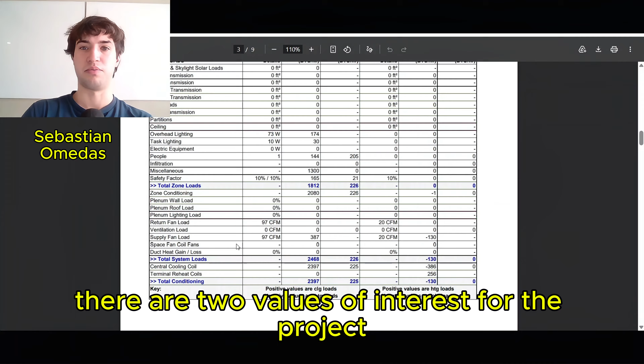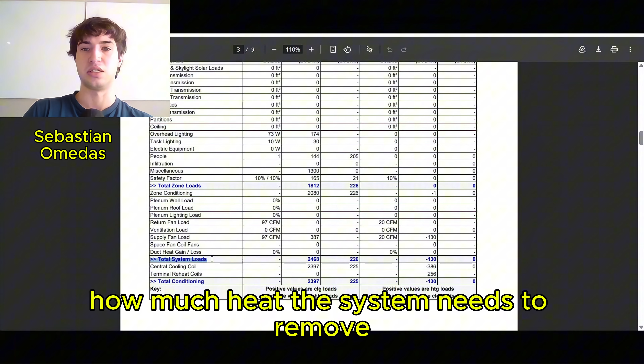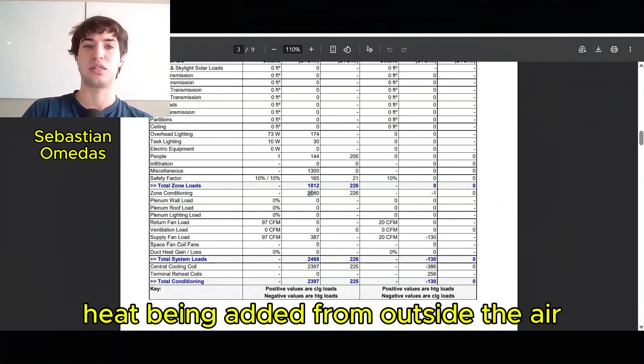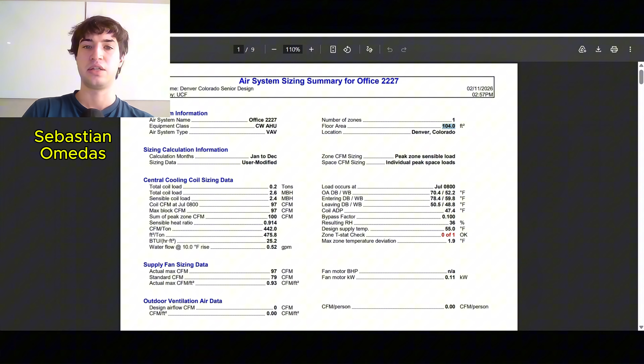There are two values of interest for the project that help the team pick which HVAC systems to install. The total system loads tell us how much heat the system needs to remove, which includes the heat added by the space calculated already, heat being added from outside air using harder calculations included here, and the heat added by the supply fan, converted to BTU per hour. The system loads are 2468 BTU per hour.